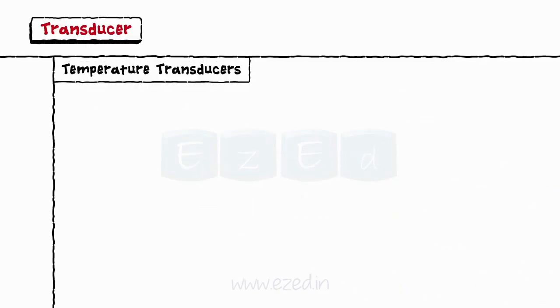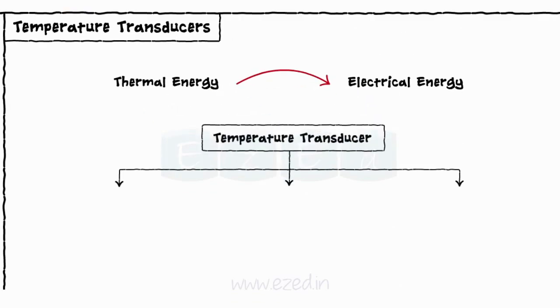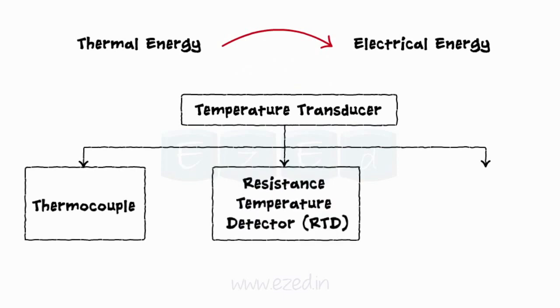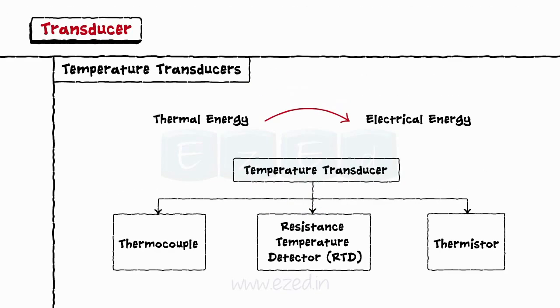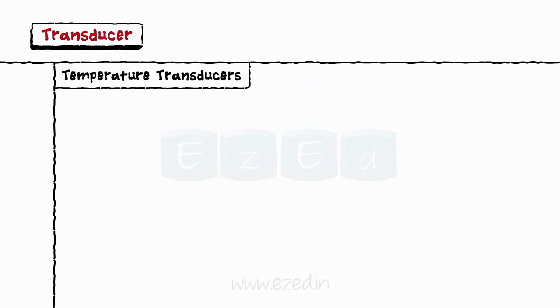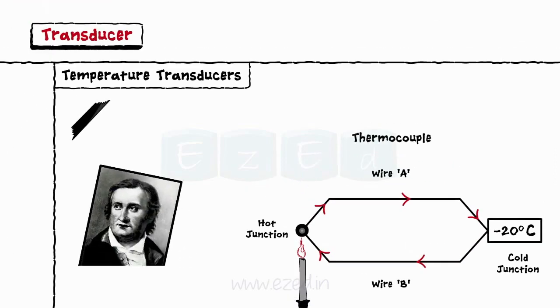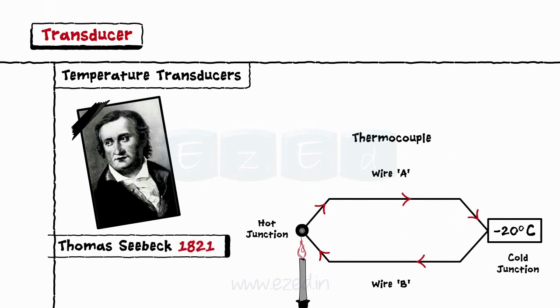Temperature transducers are devices which convert thermal energy into electrical energy. Different types of temperature transducers are thermocouples, RTD (resistance temperature detector), thermistor, etc. The first temperature transducer we will study is a thermocouple. A thermocouple circuit is formed when two dissimilar metals are joined at both ends and there is a difference in temperature between the two ends. The difference in temperature creates a small current and is called the Seebeck effect, after Thomas Seebeck who discovered this phenomenon in 1821.